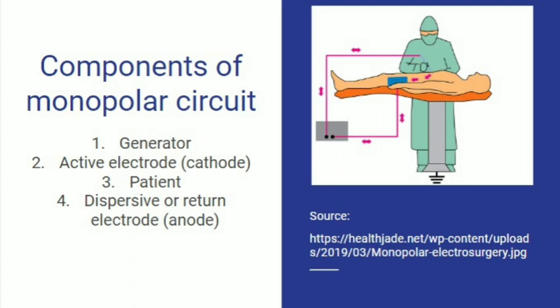You can see in the figure this is the monopolar circuit. The energy goes from the generator to the electrode, from the electrode to the patient, from the patient to the ground plate, and from the ground plate back into the generator.